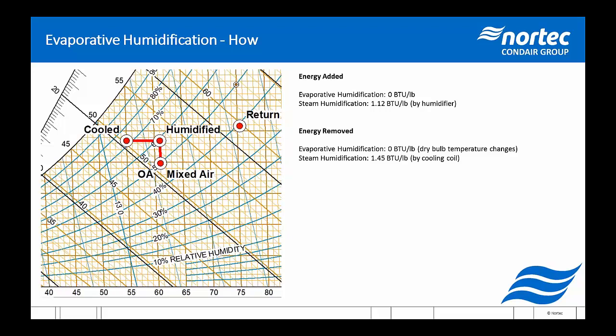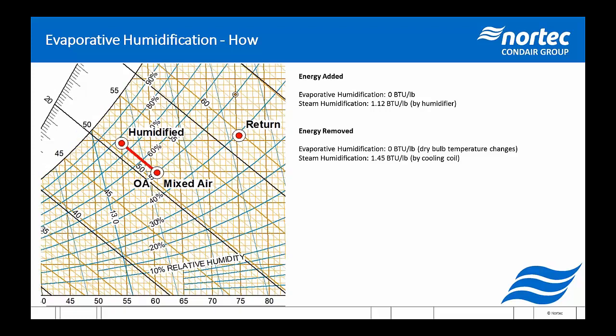So what you do with the steam humidifier is you boil water and you put it into the air, and then after your air is humidified, you still have to cool it down, so you're still running your cooling coil. And all told, you put in 2.6-ish BTU per pound of dry air. Meanwhile, with the evaporative humidifier, you get to just go straight from your outside air point, spray water in the air, and reach your set point for the air supply.